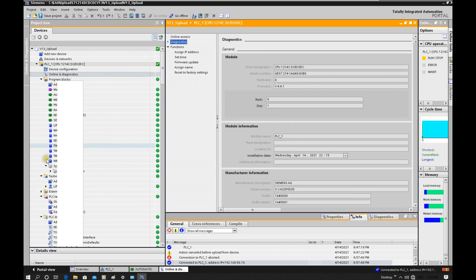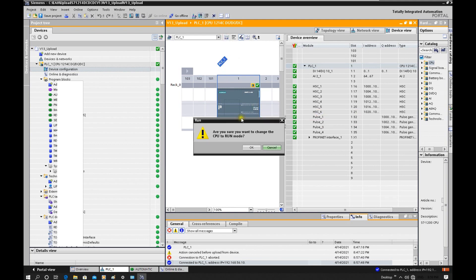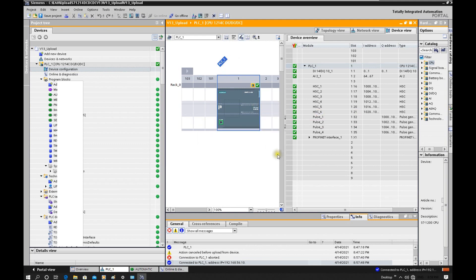We can see the IP address is still inside the CPU. Also we can see all the programs — once we go online, all the programs still match. That means upgrading the CPU firmware preserves the program, IP address, and hardware configuration — everything inside this CPU. After the upgrade, the only thing we need to do is restart this CPU. This is a really good feature.